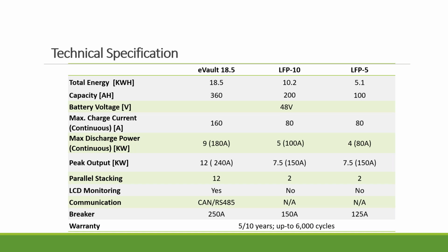Here are some technical specifications. I'm not going to go in depth. It basically tells you it's a 48 volt battery, with capacity varying from 100 to 360. Because lithium batteries have battery management systems, they come with a maximum charge and discharge current. So when you design systems, you make sure you're operating within the BMS thresholds. The 5 and 10 you can stack 2, and the eVault you can stack up to 12. The eVault also comes with LCD monitoring as well as communication.